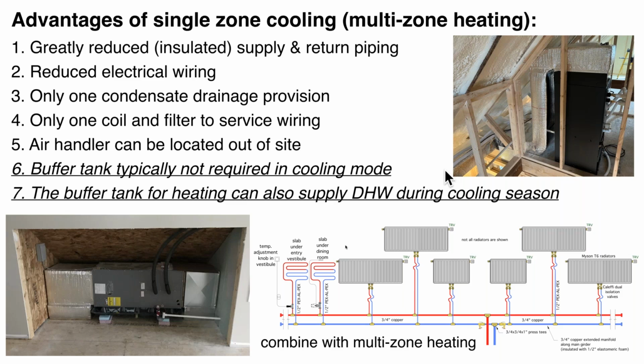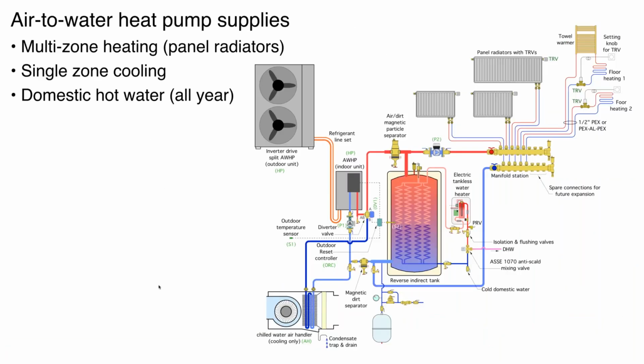So, here's an example of multi-zone heating where we've got panel rads and some floor heating circuits, and we've got a single variable speed circulator down here that handles all that. So we can do extensive zoning on the heating side and still combine it with single zone forced air distribution on the cooling side. Again, a schematic. This happens to show a split system air to water heat pump. You can see here we've got a diverter valve. So in heating mode, we would direct our flow over into our tank. In cooling mode, we're coming down through the air handler. And notice the buffer tank is not involved in cooling mode at all.